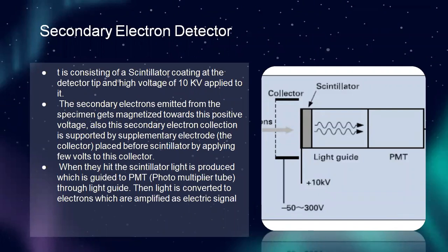Next, I will discuss the secondary electron detector. It consists of a scintillator coating at the detector tip with a high voltage of 10 kV applied to it. The secondary electrons emitted from the specimen are attracted towards a positive voltage. This secondary electron collection is supported by a supplementary electrode — a collector placed before the scintillator — by applying a few volts to this collector. When they hit the scintillator, light is produced which is guided to a PMT (photomultiplier tube) through a light guide. The light is then converted to electrons which are amplified as an electric signal.